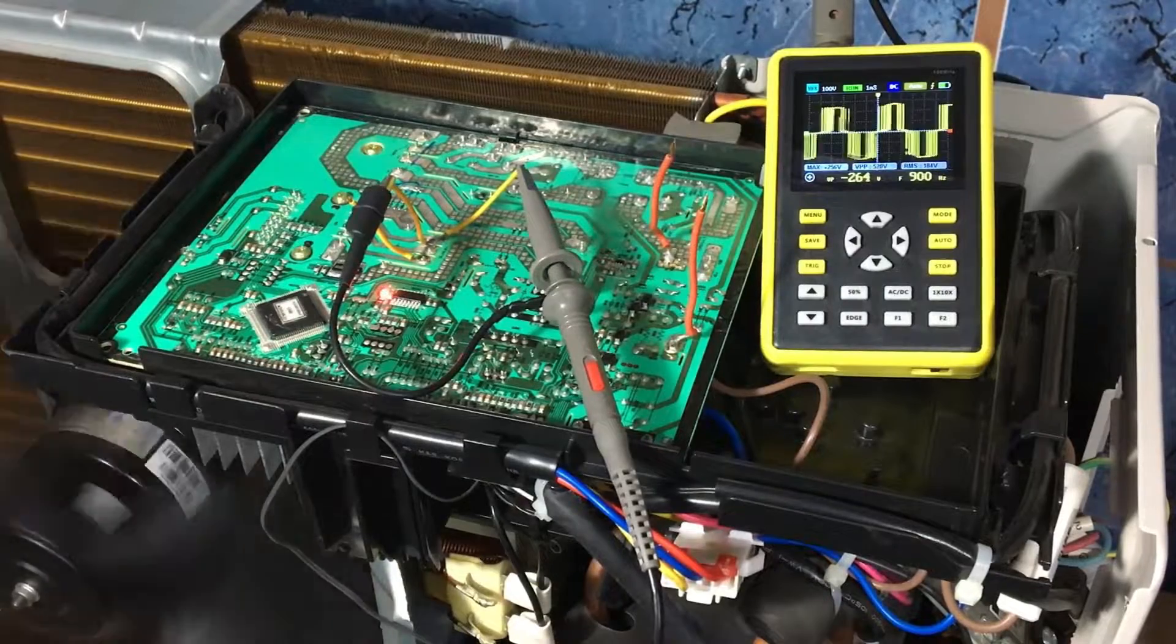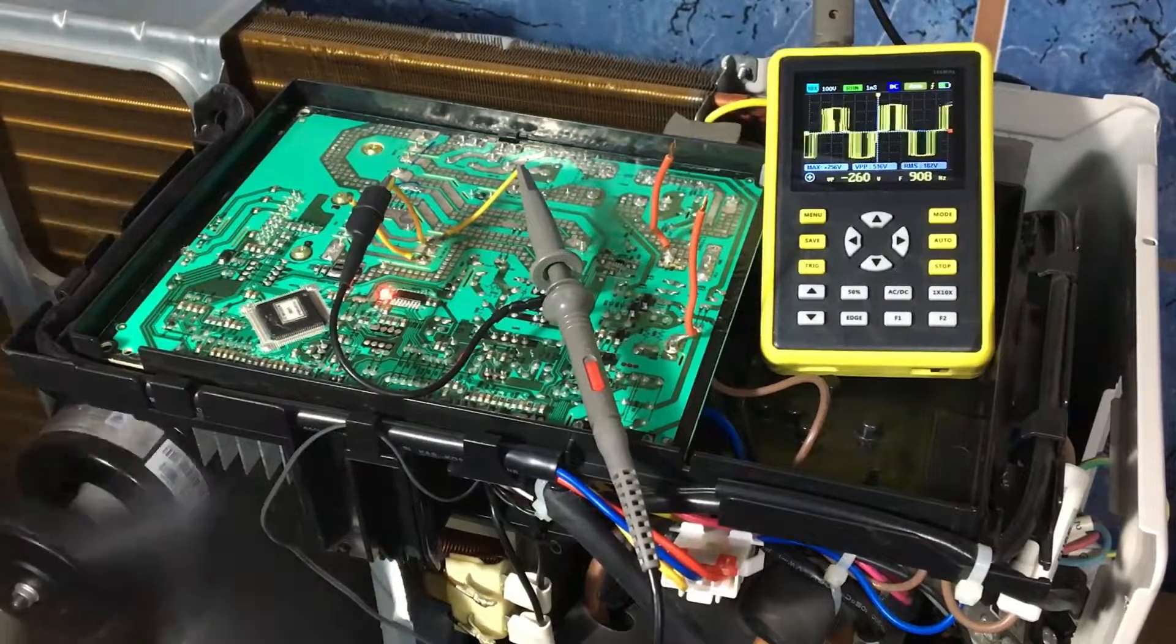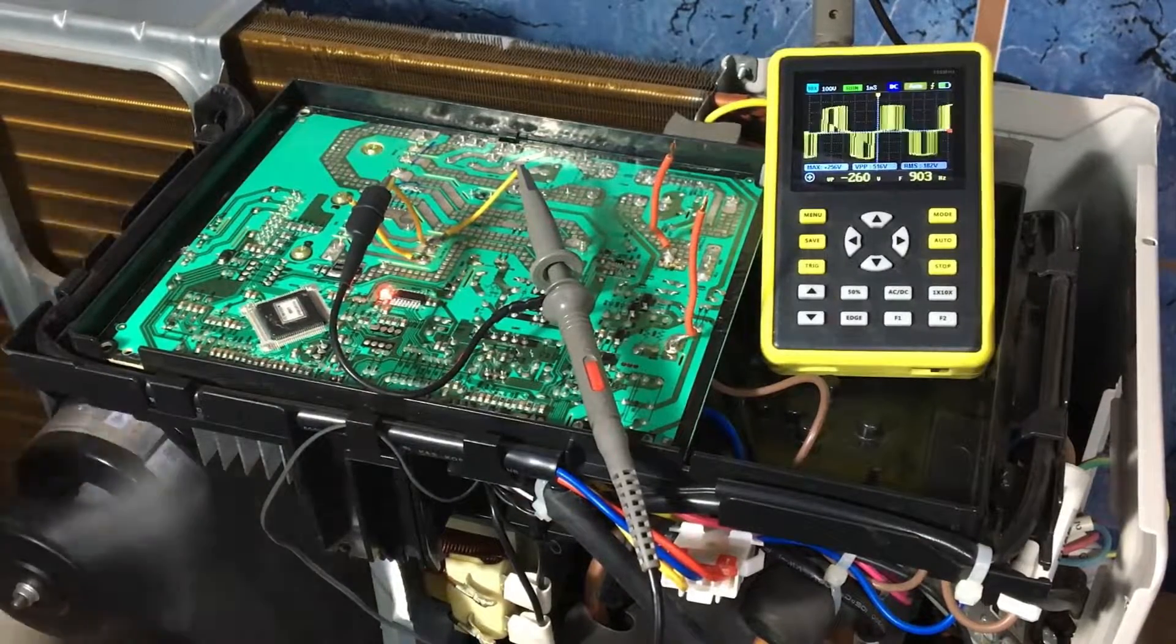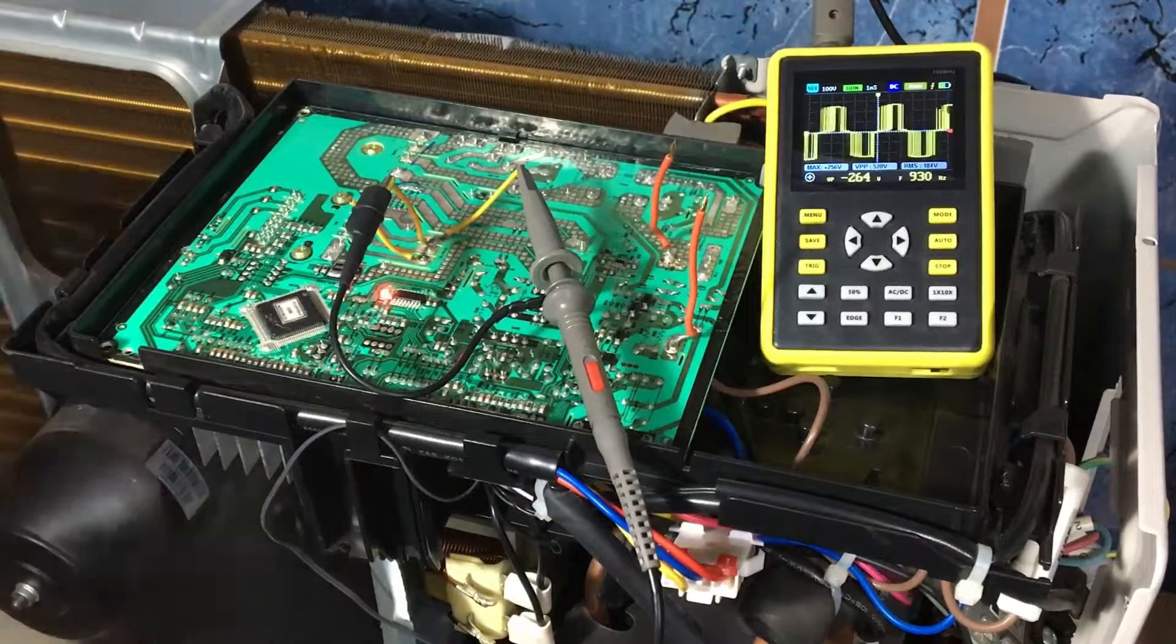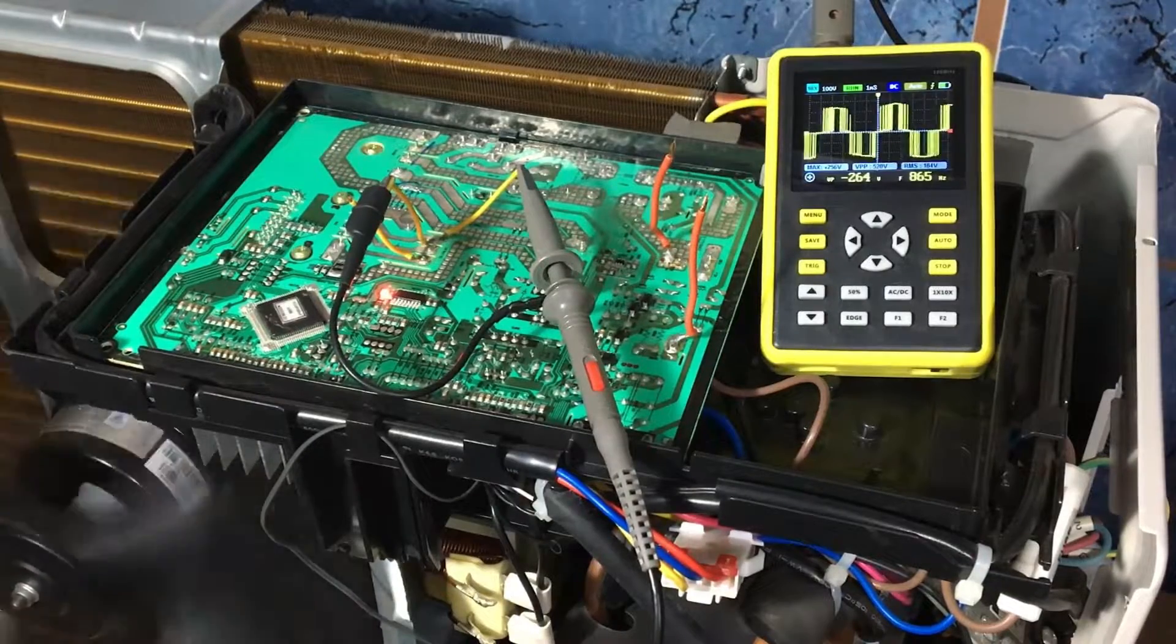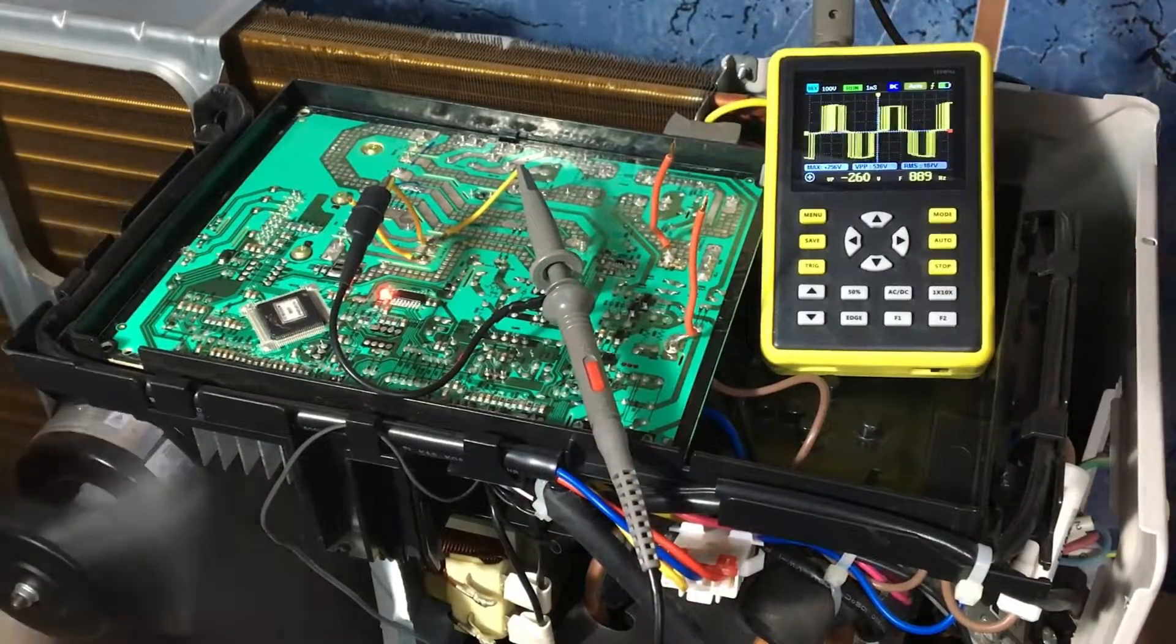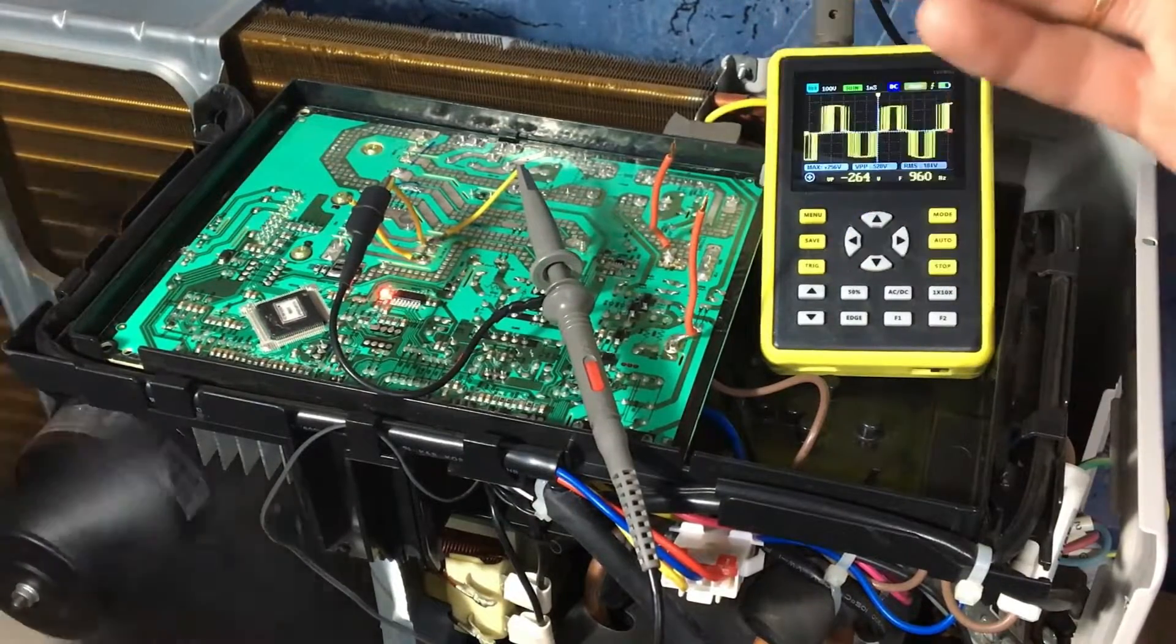We will do tests to be able to know what measurement we have to get in case the compressor is not there and to be able to know that the IPM is working well.